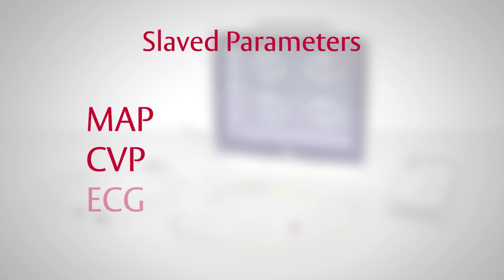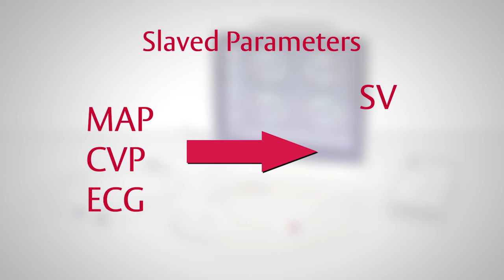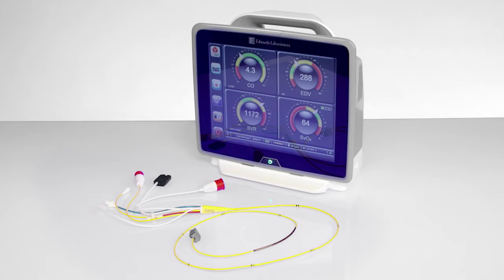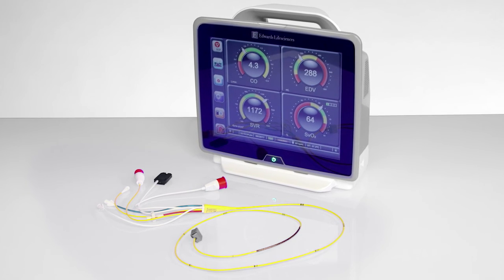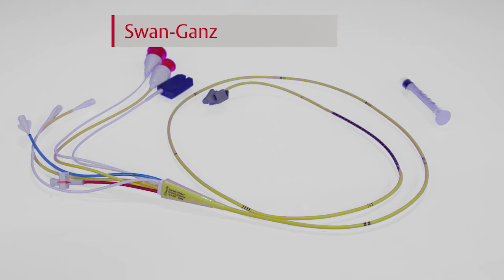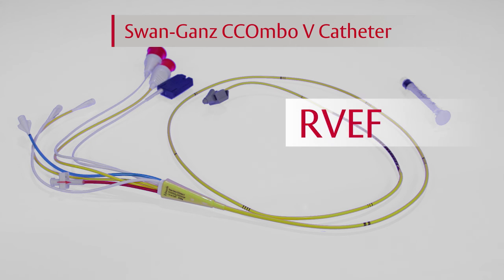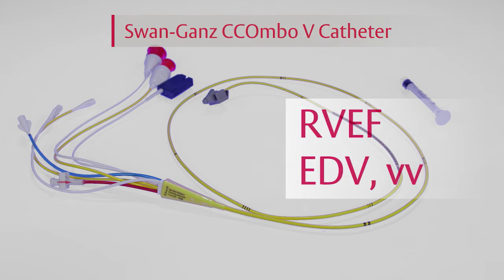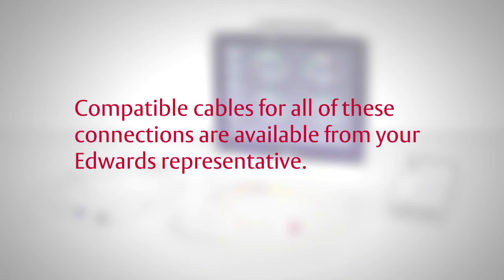MAP, CVP, and ECG can be slaved from any external patient monitor which meets the signal input specifications. These parameters can be used during continuous cardiac output monitoring to derive SV, SVR, RVEF, and EDV. In addition to the mentioned slaved values, a Swan-Ganz CCOmbo V catheter is necessary to display the volumetric parameters of RVEF and EDV-VV.